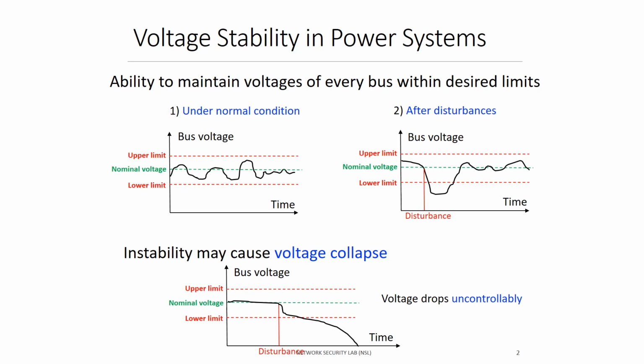Voltage stability in a power system refers to the ability of the power system to maintain voltages of every bus within desired limits. It has two cases. One is when the power system is under normal condition. Every bus should have voltage within the range. Another case is when the power system has a disturbance. Then the voltage may drop below the lower bound temporarily, but if the voltage can go back to the region, then it's still stable. Otherwise, the voltage may drop uncontrollably and cause voltage collapse.